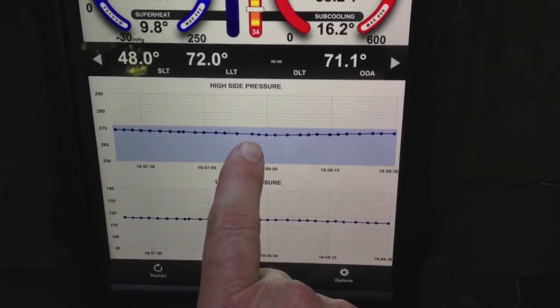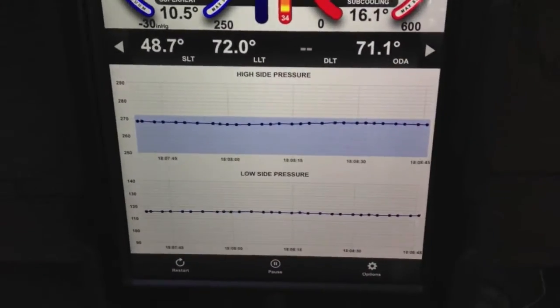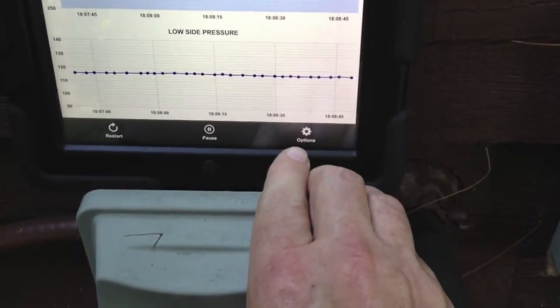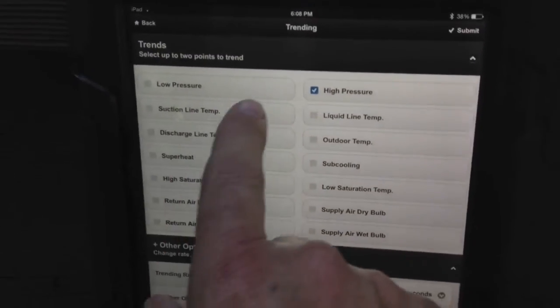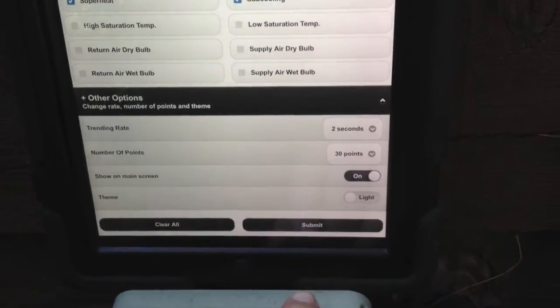It's a little bit high on this band right now. The most likely cause is I have some dirt on my condenser — it's not filthy but definitely not spotless. It ran all last summer and I haven't cleaned it yet. If we wanted to change anything on the trend, we'll go to options. I'm going to take off high and low pressure and switch to superheat and subcooling, then hit submit.